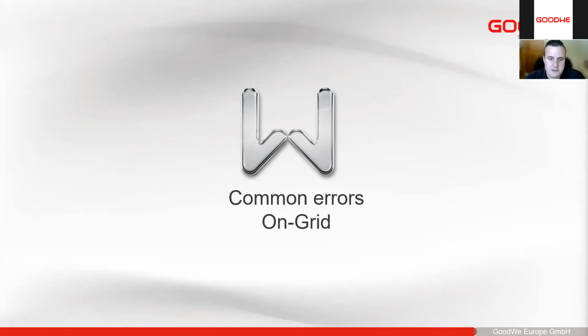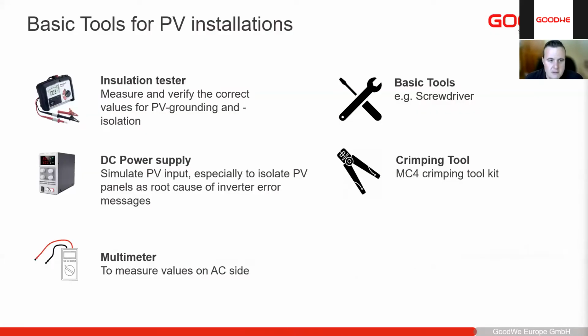So now we move on to the on-grid errors. So again, the basic tools. For the on-grids, a DC power supply is also nice to have. Very often these inverters only power up from the DC supply. So if it is a problem on the modules or anything like that, it's nice to have a DC supply to test it. But we don't require you to have that. If the device is not coming on, we'll just send you a new one.